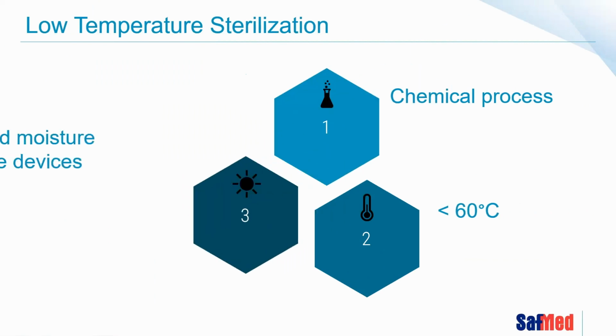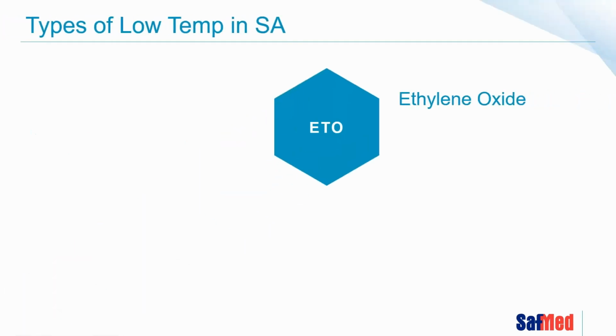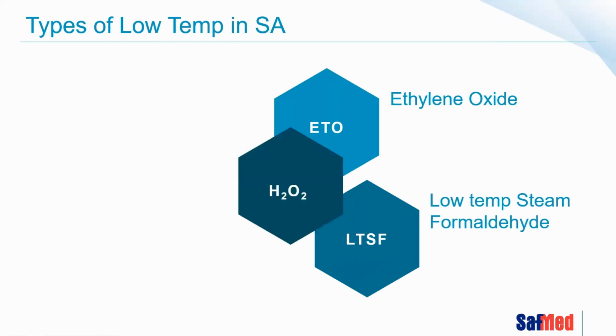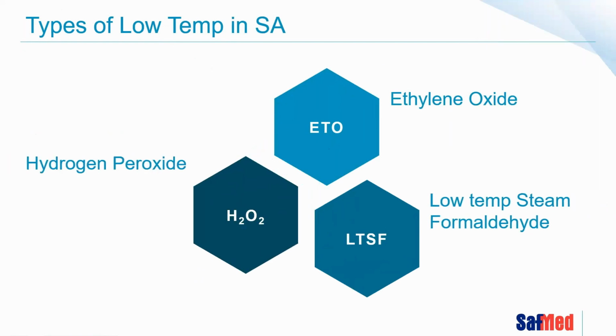Low temperature sterilization is a chemical process. Steam sterilization is a mechanical process. Low temperature sterilization is a chemical process. It's sterilization that generally takes place at less than 60 degrees C, and as we said already, for heat and moisture sensitive devices. In the South African hospital setting, you're likely to come across these three modalities in essence: ethylene oxide, low temperature steam formaldehyde, and hydrogen peroxide sterilizers.